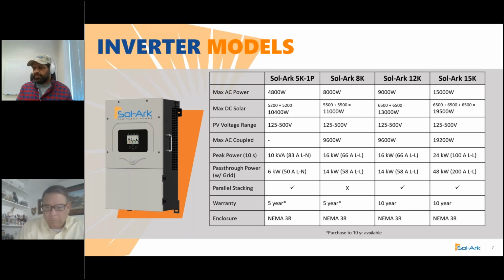Now, of course, when you go off grid, like when the utility goes down, you don't have 200 amps anymore -- you have about 62.5. But now the door is open so you don't have to make a whole new sub panel or critical load panel. Instead, you can just connect directly to the main service panel from the load output of the Sol-Ark 15K, and then use some kind of load management device to reduce loads immediately when there's a utility failure.